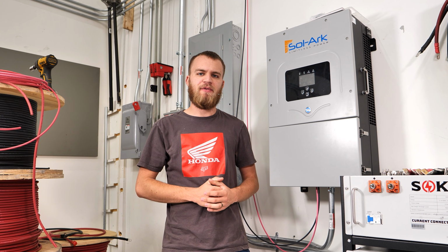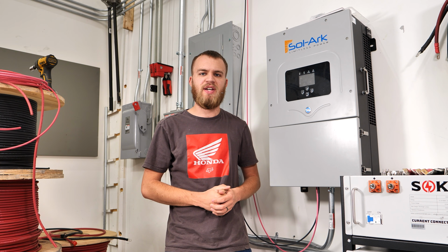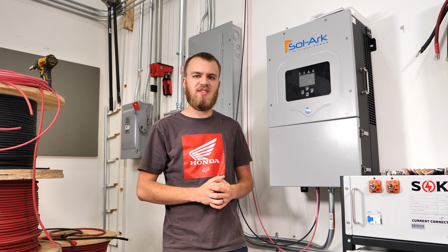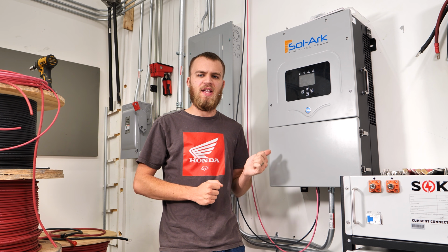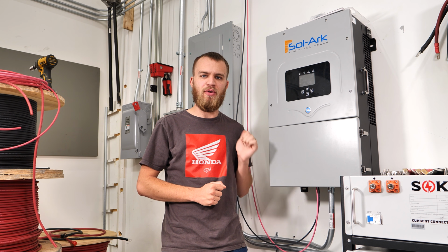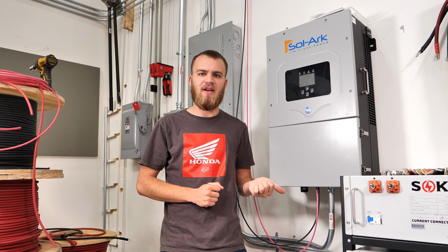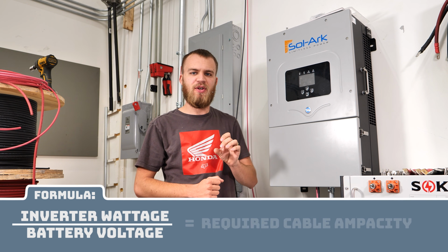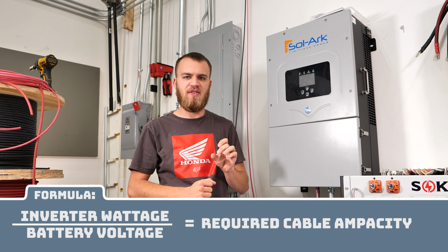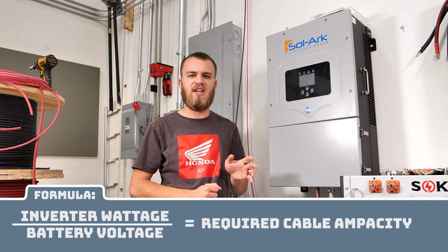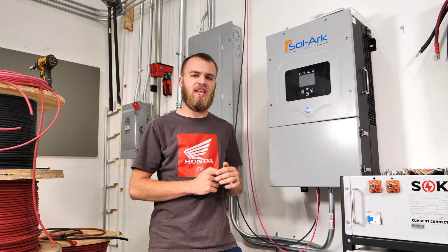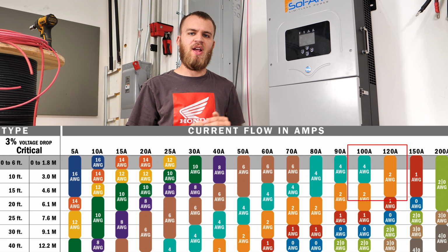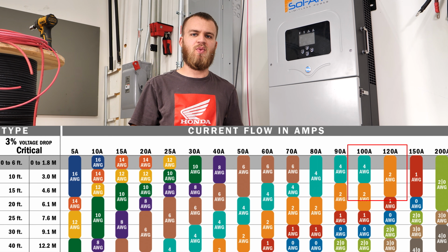So to wire these up, the first thing we need to figure out is what size wire we need. So in today's example, we're using a Sol-Ark 5K. The maximum this can take in and put out to the battery is 5,000 watts. So if we take 5,000 watts and divide it by 51.2 volts, which is the nominal voltage of these batteries, we get just shy of 100 amps. So if we then take that number and look at our chart, that's going to give us a 2-gauge wire.